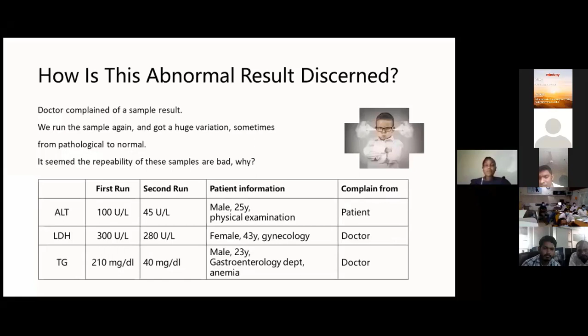You can see that in all the first runs here, the reaction response would be very, very high. So we went deeper to troubleshoot: is it the instrument? Is it the reaction principle? Are they related? What is it that really happens? So we did an instrument analysis to check its performance qualification, and it was okay. For LDH, as displayed on my left curve, you can see the calibration is normal.